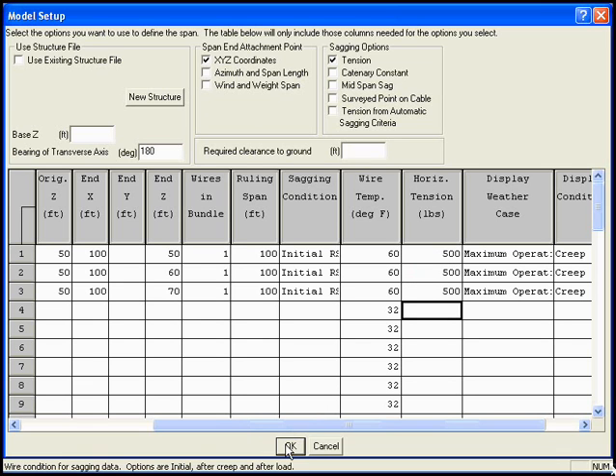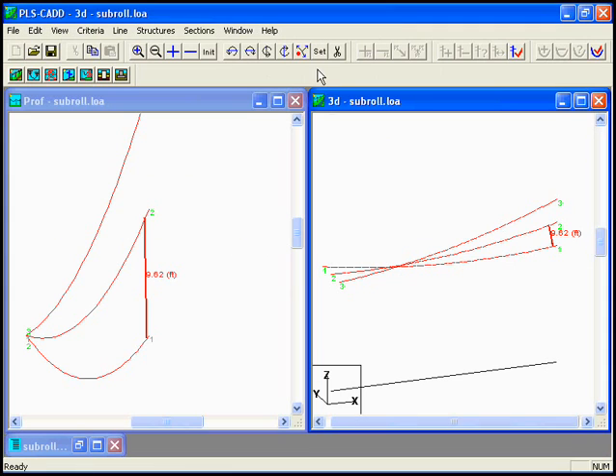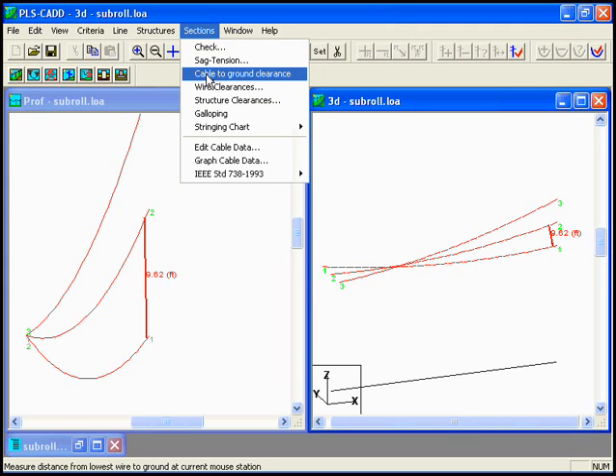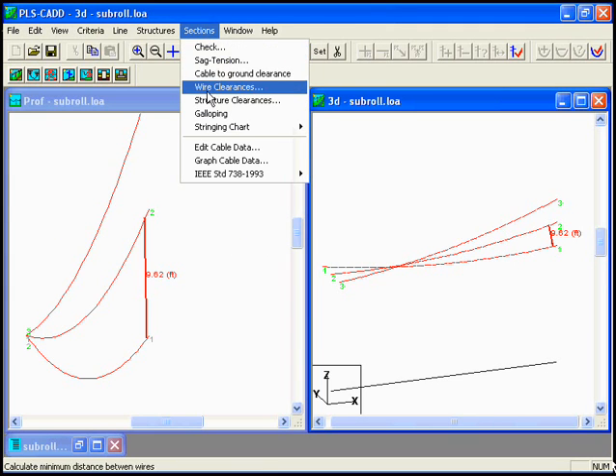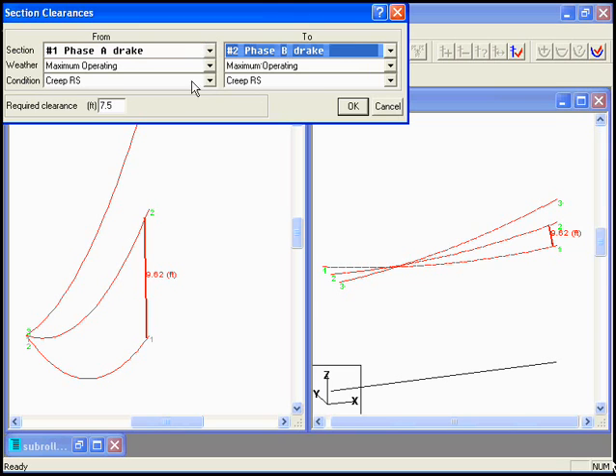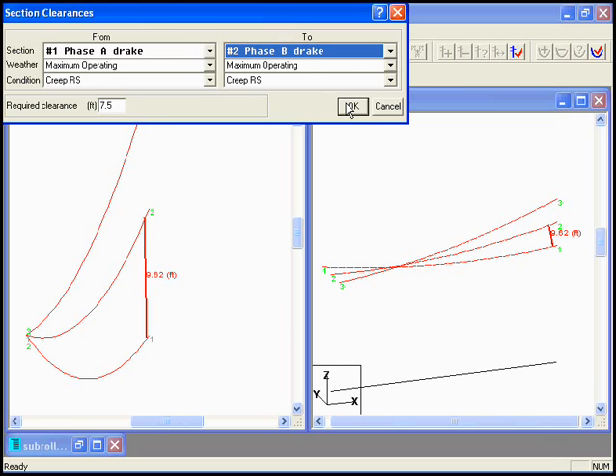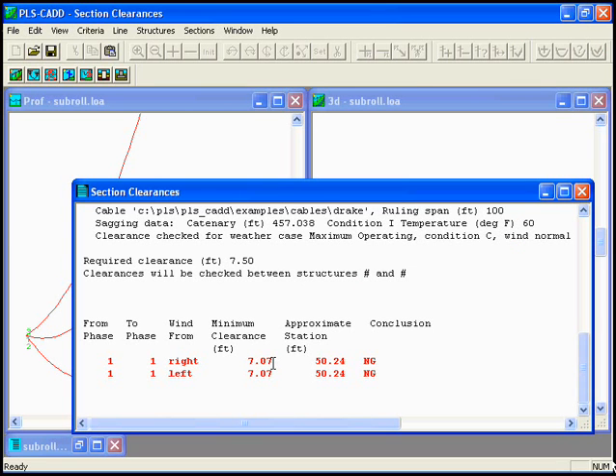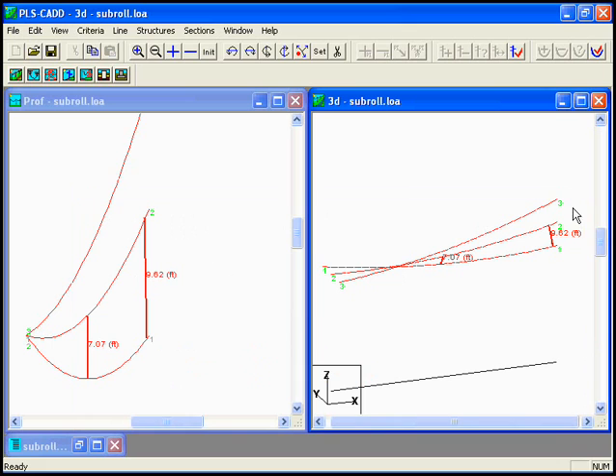Now we can instantaneously see the new sags of the wires. And now let's do a Section, Clearances. And we'll go from Phase A to Phase B again, maximum operating, 7.5 feet. Now we have a clearance problem. 7.07 feet is all we have at station 50.24. We close out that. We can graphically see where that clearance violation is.